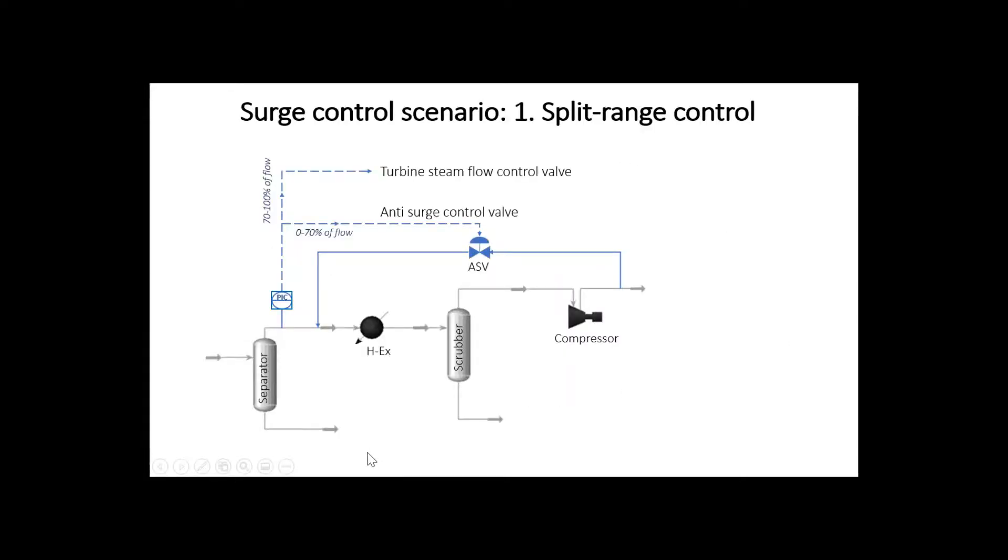Let's now look at one example where we use split range control system. In this example, the mixture is separated into gas and liquid fractions in the separator, then the separated gas goes through the cooler and the gas scrubber where the minor amount of condensed liquid is separated. Then the dry gas enters the compressor and the compressed gas flows downstream.